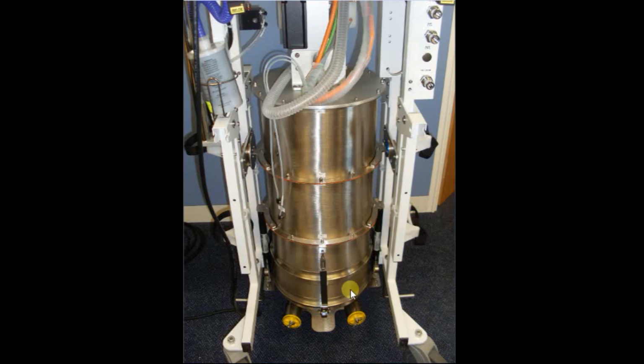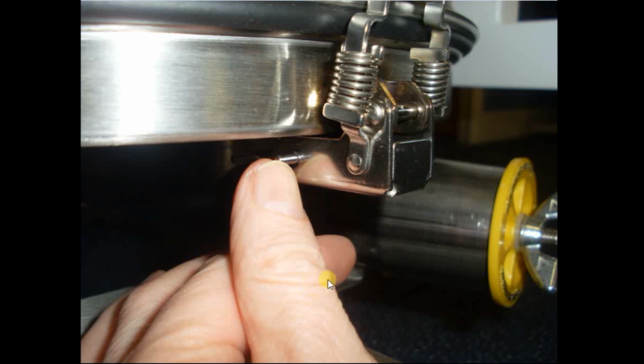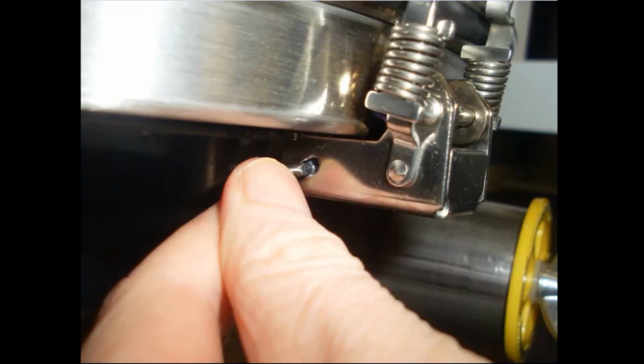But now we're going to have a look at the soda lime tray in the Tafonius Junior and go through its removal process. As I mentioned before, there are 3 clasps that hold the soda lime tray in place. Here's one at the front, and we saw one at the back, and we saw the 2 at the front earlier on. To undo these clasps, there's a little bracket clasp here that needs to be undone in a particular way. If you get down and look at the bottom of the machine, the bottom of this little clasp has a sprung rod or spigot here, which you have to push down away from the front of the machine to release. This shows the spigot being pushed away, and now it's in a position where the clasp can be pulled down and released.